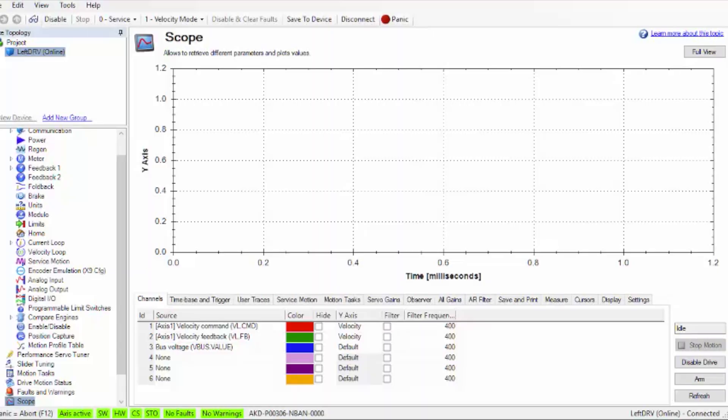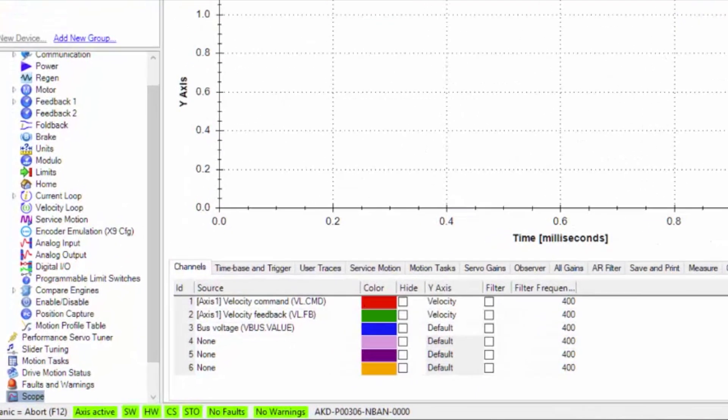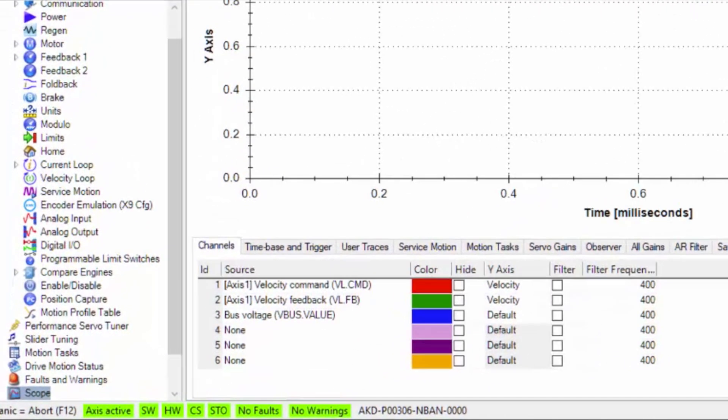In our scenario, we suspect that drive bus voltage is dropping below 90 volts DC. This will cause an under voltage fault 502.